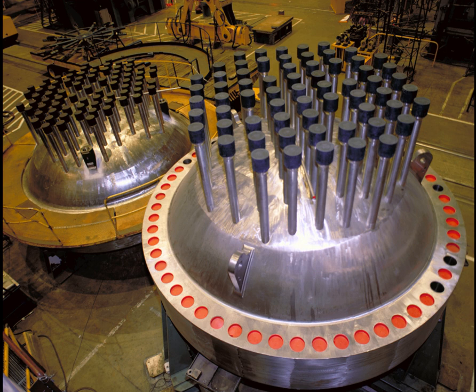Some common steam generator arrangements are U-tubes or single-pass heat exchangers. In a nuclear power station, the pressurized steam is fed through a steam turbine which drives an electrical generator connected to the electric grid for transmission. After passing through the turbine, the secondary coolant is cooled down and condensed in a condenser. The condenser converts the steam to a liquid so that it can be pumped back into the steam generator, and maintains a vacuum at the turbine outlet so that the pressure drop across the turbine, and hence the energy extracted from the steam, is maximized.